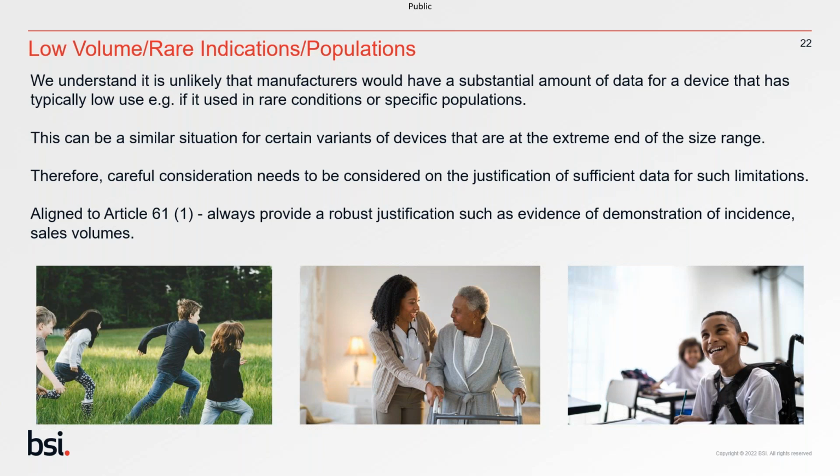So evidence that could be used, for example, where perhaps the device is seldomly used, could include the sales volumes. You may say, well, we've only sold 12 of this size range last year, and the previous year it was 6. So you can see that we're not going to get the sufficiency of data that we need, but we do have the quality data and we do have some evidence to suggest this, and we are addressing it in our post-market clinical follow-up plan to gather more data to support that.